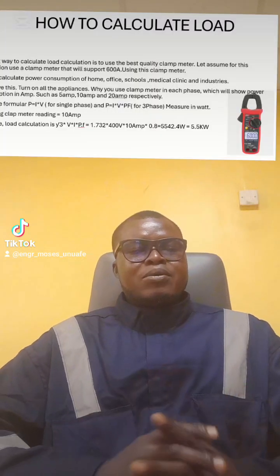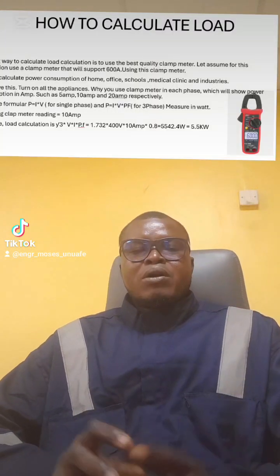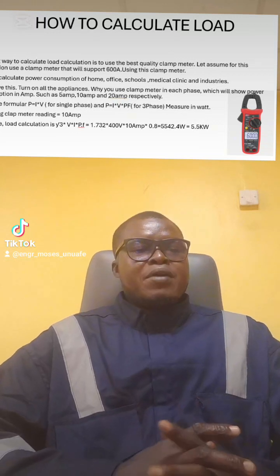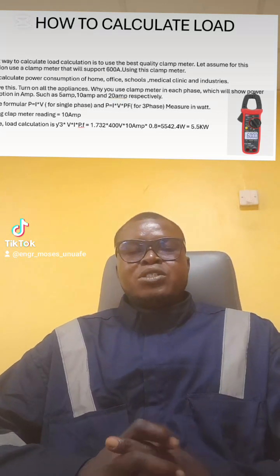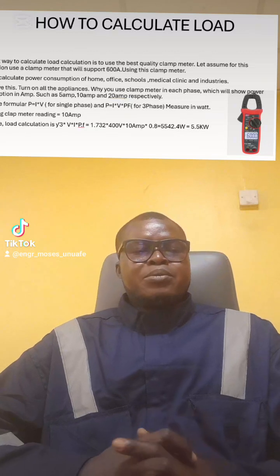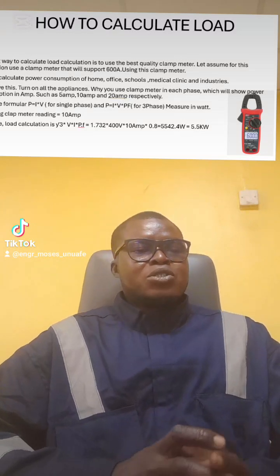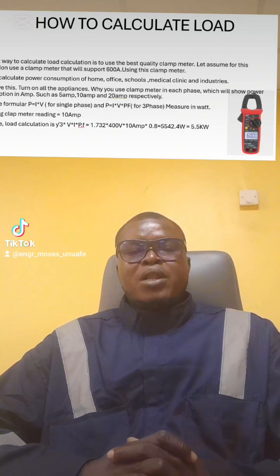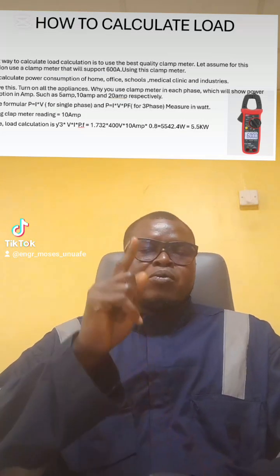For us to achieve this, you have to first turn on all your electrical appliances and, using a clamp meter of 600 amp, measure the current. Now, let's take this scenario. Assuming your clamp meter gave you a reading of 10 amps for each of these three phases, then you have to substitute it into the formula which is shown above.